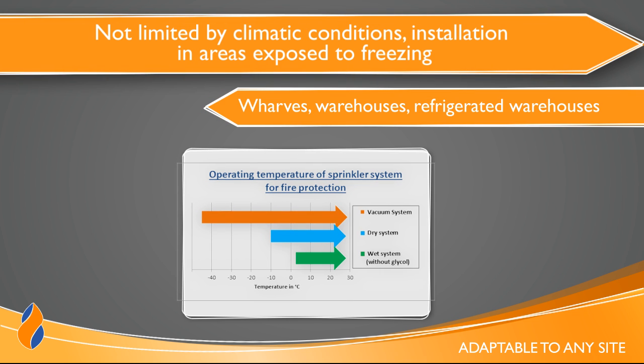The VACTEC system can be installed whatever climatic conditions are, so it can be installed in very cold regions or areas. The VACTEC system has a wide operating range unlike traditional systems. The wet system is sensitive to freeze. It can operate under negative temperatures only if glycol is added. The dry system is operational from -10 Celsius degrees or 14 Fahrenheit degrees, but it remains sensitive to freeze due to condensation. The VACTEC system, for its part, can operate with very negative temperatures without freezing. Sites exposed to freezing and very cold areas are then effectively protected against fire.